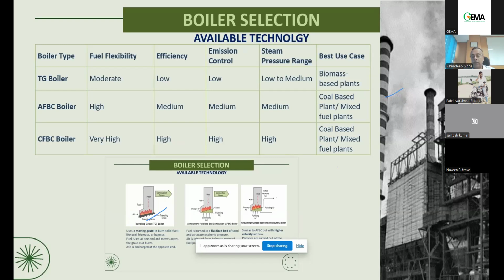Obviously the steam pressure range, I will come to the steam pressure range after this, and the capacity also there is a restriction. You cannot go for a TG fired boiler of a 200 TPH capacity or 150 TPH capacity, because otherwise it will be a very big boiler. So there are certain restrictions, but it will be cost effective for a lower TPH and lower capacity plant, and particularly when you are going for a biomass plant.